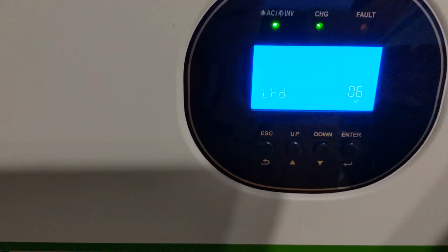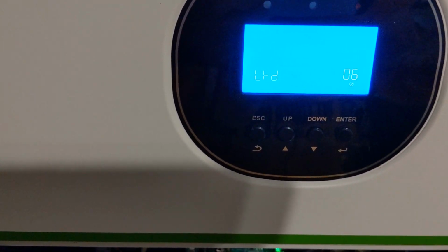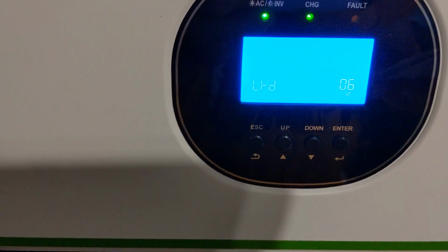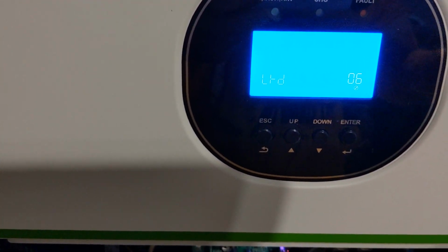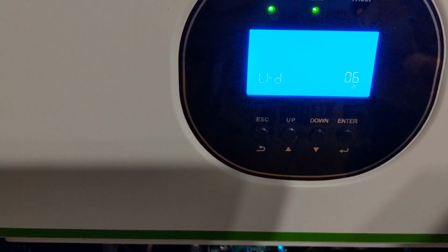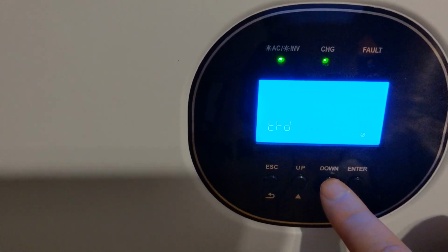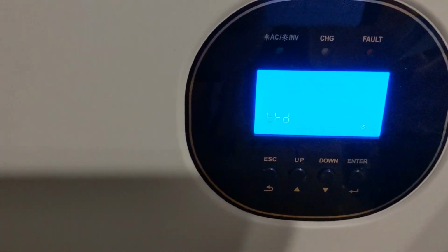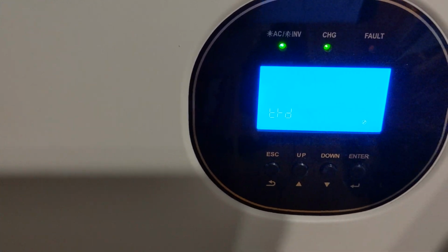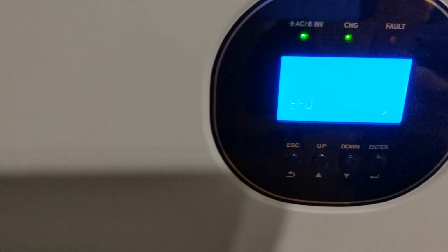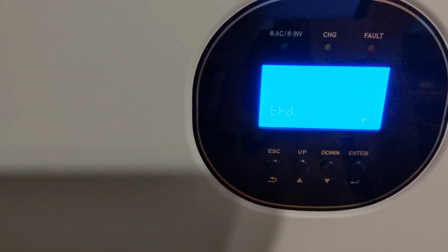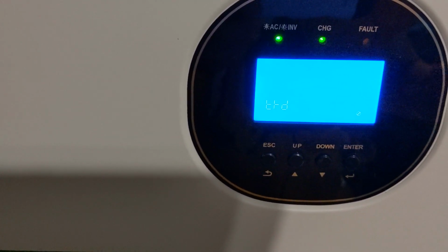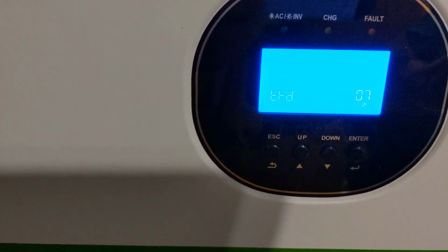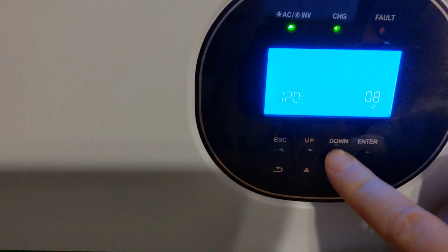So in this guy here, this is the auto restart if overload. I have it in its default setting of disable. That way if something massively overloads the unit and it shuts it down, I can turn things back on, find out what caused it and make sure I don't damage anything, so it's not trying to just constantly cycle itself. This is the restart, and this is also set to disable. This is basically the auto restart if it gets too hot. Again, that allows me to make sure that if there's a major cooling issue or something of that sort, I can correct it so I'm not damaging the units.